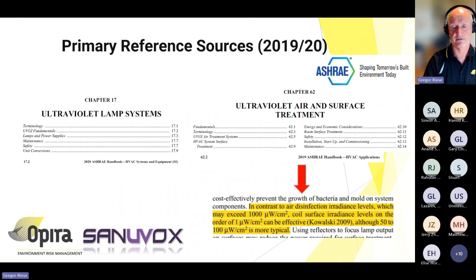And this is a Sanuvox sizing software, and when we go ahead and we're targeting Aspergillus niger, it's actually one of the hardest to kill. It's a very tough little fungal spore. So we choose one of the toughest, or we choose the toughest, and then we size accordingly. And we're targeting 250 microwatts per centimetre squared on a coil face. So it's sort of 2.5 times what ASHRAE and Kowalski are recommending that you need. So there's a sort of a safety margin there, essentially.